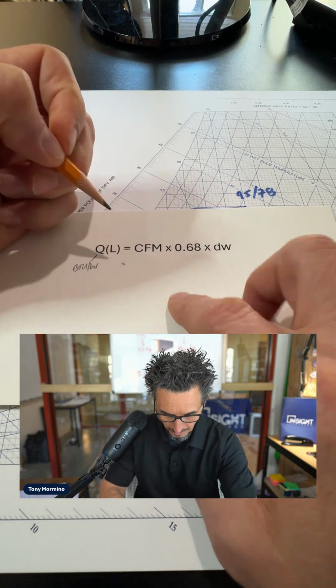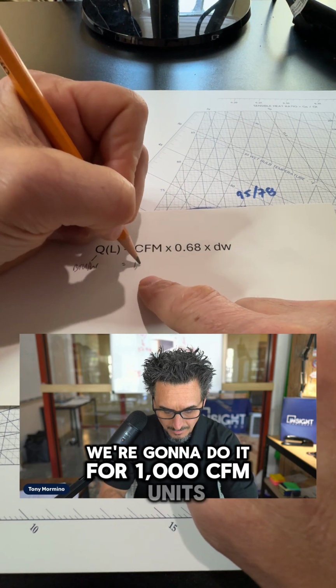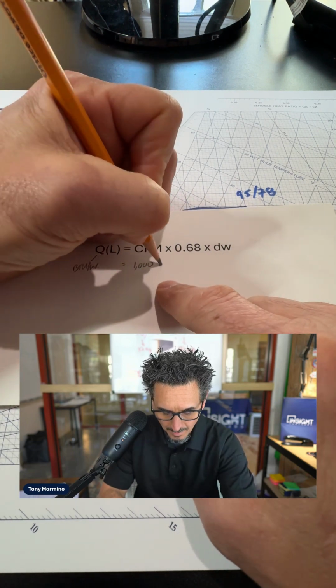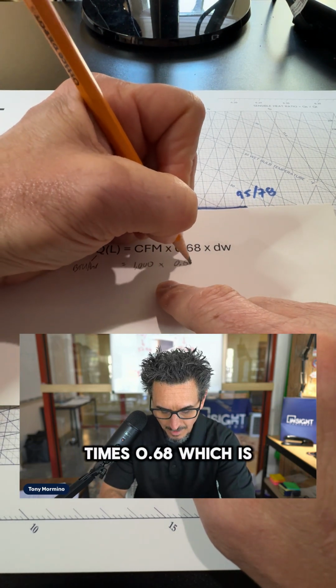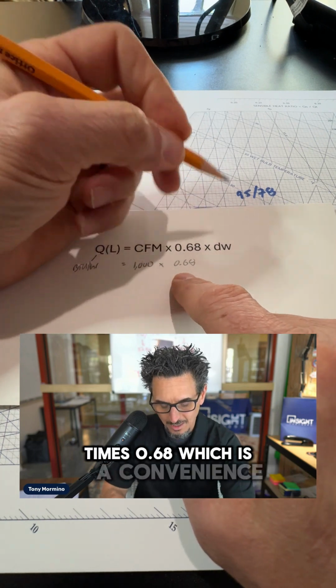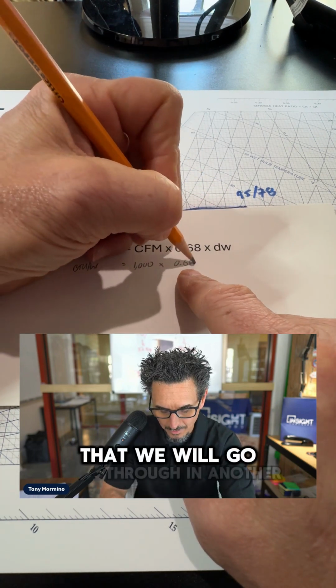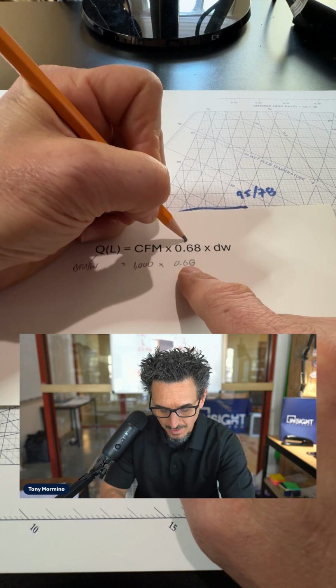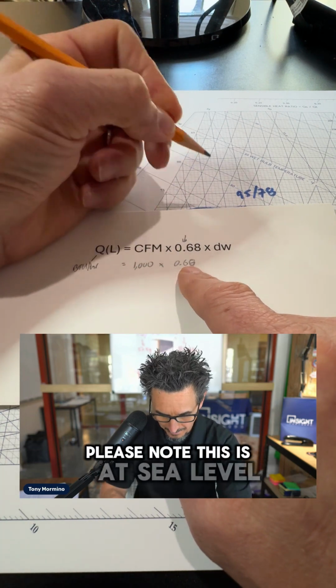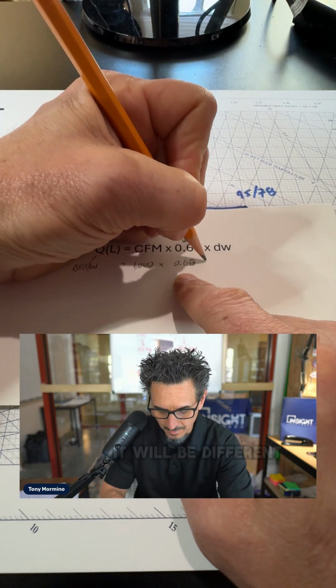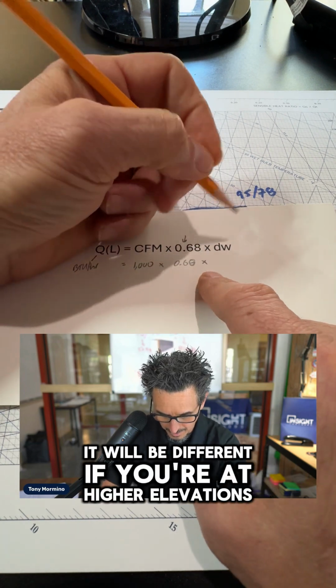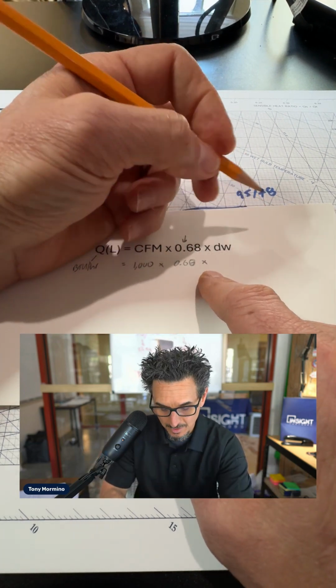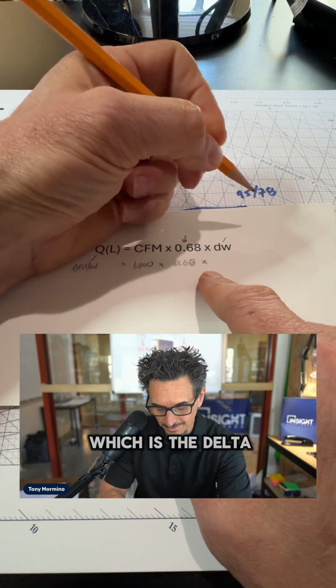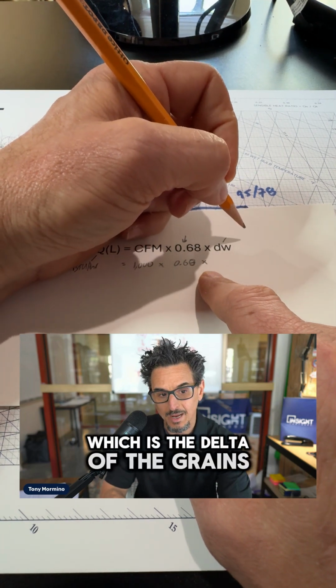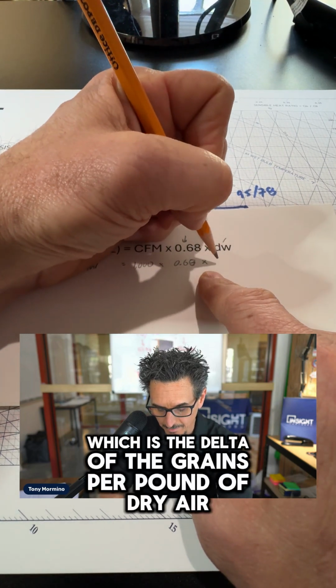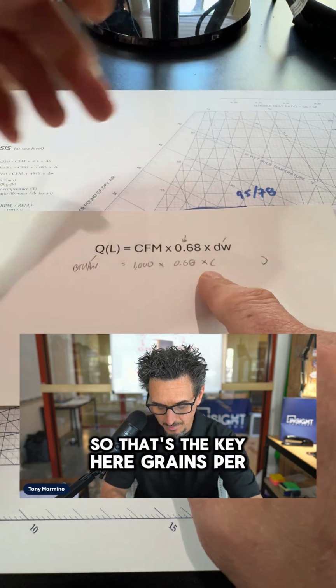equals, in this case, we're going to do it for 1,000 CFM units times 0.68, which is a convenience factor that we will go through in another episode. Please note, this is at sea level. Okay, it will be different if you're at higher elevations, times dW, which is the delta of the grains per pound of dry air. So that's the key here, grains per pound of dry air.